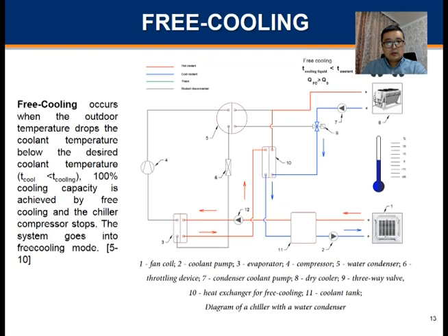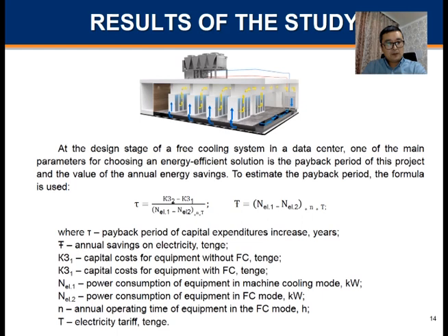Free cooling occurs when the outdoor temperature drops the coolant temperature below the desired temperature. 100% of the cooling capacity is achieved by the free cooling and the chiller compressor stops. The system goes into free cooling mode.